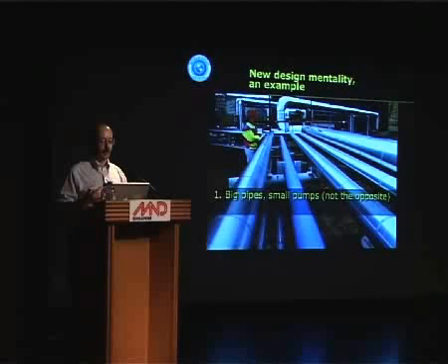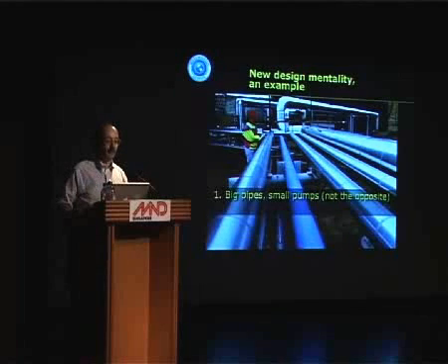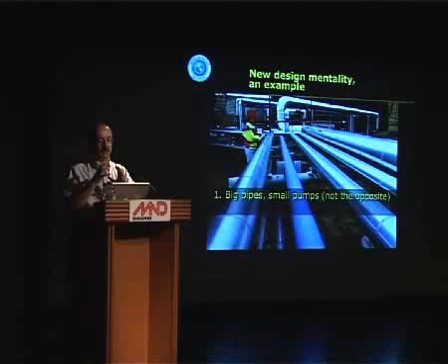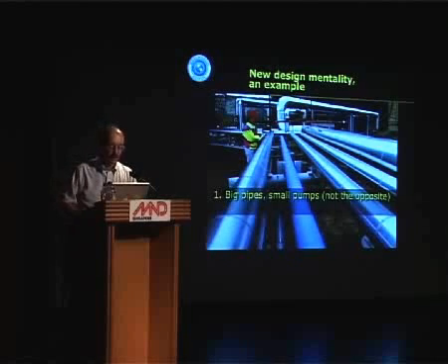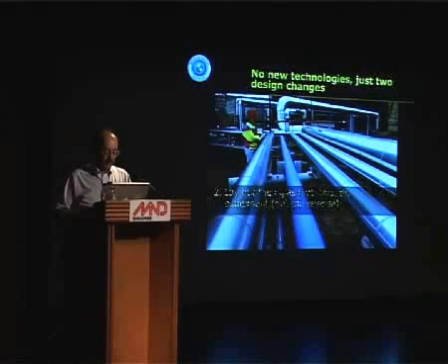But this is methodologically just as wrong as not counting the ability to eliminate the furnace in my house when you think about how much insulation there should be. Because after all, the pumps, the motors, the inverters, the electricals all have to be big enough to overcome the friction in this piping system. So their size and roughly their capex will go down as nearly the fifth power of pipe diameter. But the fatter pipe costs more as only about the second power of diameter. So when we conventionally optimize the pipe as a component by itself, we're pessimizing the system. If we optimize the whole thing together, we'll use fat pipes, tiny pumps and motors, and the total capex will go down. Not rocket science, just good Victorian engineering rediscovered.